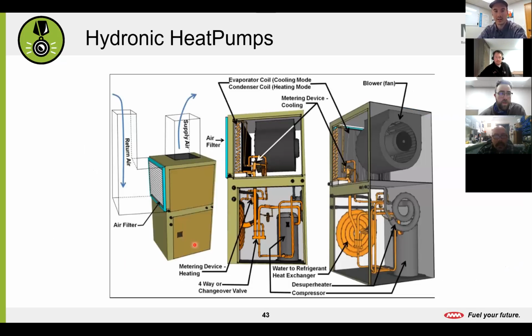Okay. So the next slide here. This is a pretty good diagram of a hydronic heat pump. When we keep talking about how the air absorbs energy and puts it into refrigerant, and then the refrigerant puts it into water, we're never mixing refrigerant and water. That's sometimes a common misconception. This little coil right here, we'll call that our heat exchanger. It's a tube inside of a tube. One tube runs refrigerant through it, and another tube runs water through it. And they're just conducting heat through the metal. They're not mixing, blending, or doing anything like that. And if they are, you've got a failed heat exchanger and you've got to fix that.